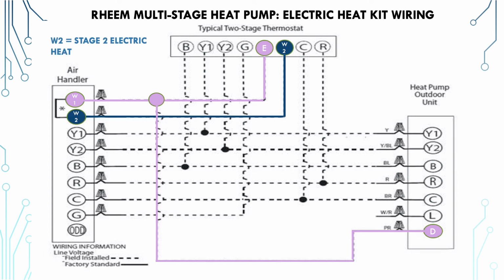Now, when you have second stage electrical heat, there's two ways that this can be done. The most uncommon way that it's done, because there's usually not enough wires at the thermostat, is to actually put a wire in the W2 contact and run it down to the second wire in the air handler for the other sequencer kit. And now this particular schematic is showing that W1 and W2 are jumpered together, and that is the alternative.